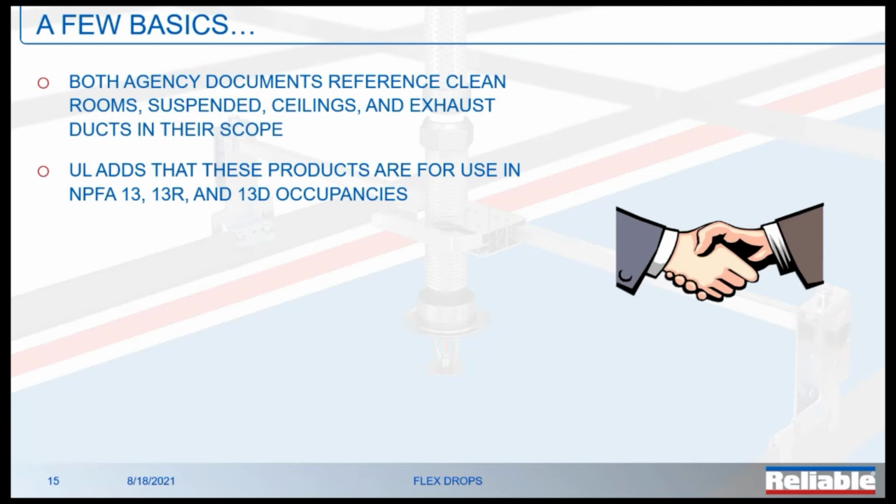There's nothing that says you can't, unless you're in the UL world and you look at this and go, wait a minute, 13R and 13D, I don't think there are too many foam systems referenced in those documents. So the answer to that question, at least in the UL world, had to be no. They're for use in these particular occupancies. So keep that in mind.